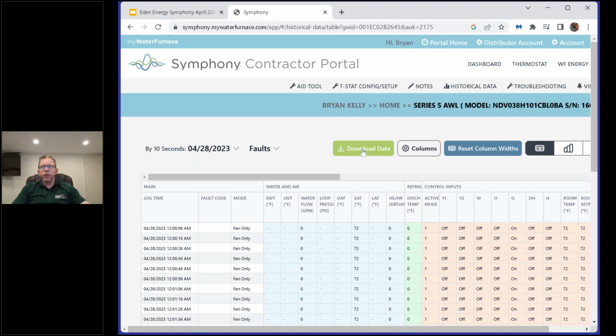As much as we're talking about the power this offers remotely, there's also tremendous value locally. There will be times when you've got service techs on site, whether for regular maintenance or just in the area. Generally speaking, on a WaterFurnace you don't need to put your gauges on the system—you verify the water side and the air side or load water side, and if those check out, you don't need gauges, because those can't check out if you have a refrigeration issue.